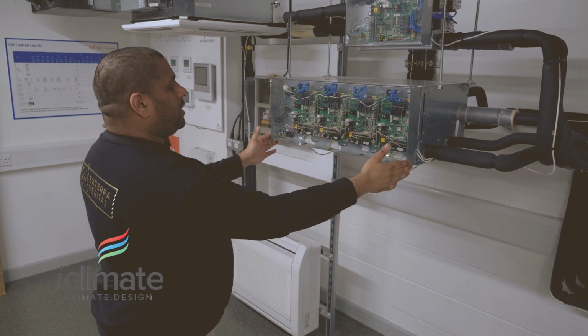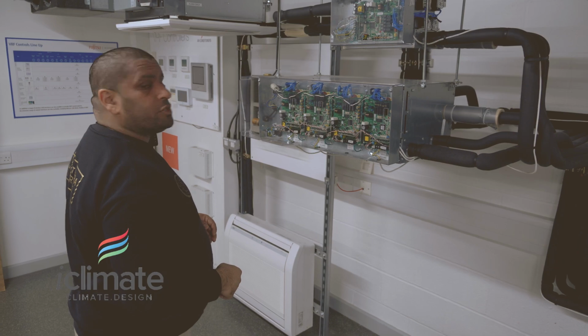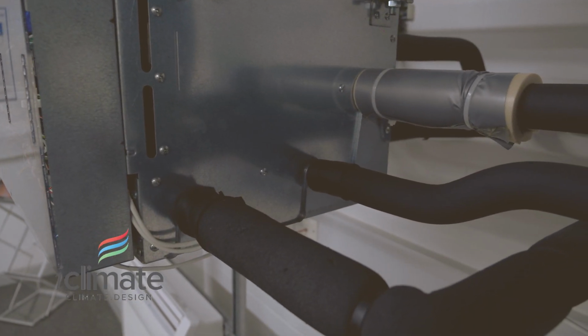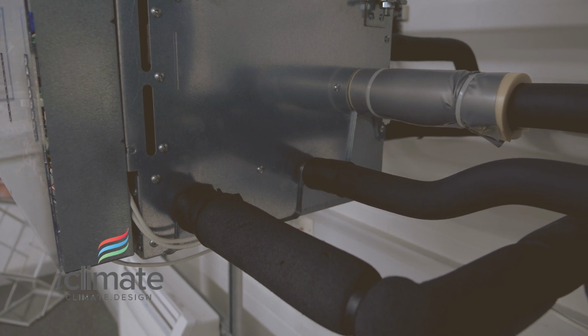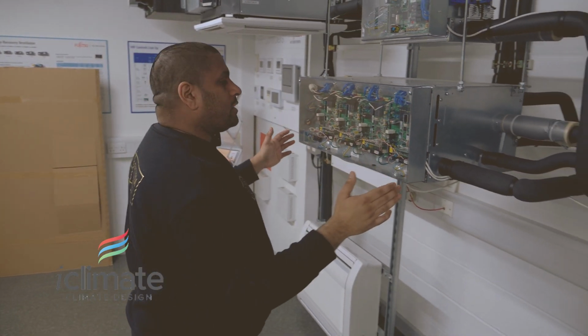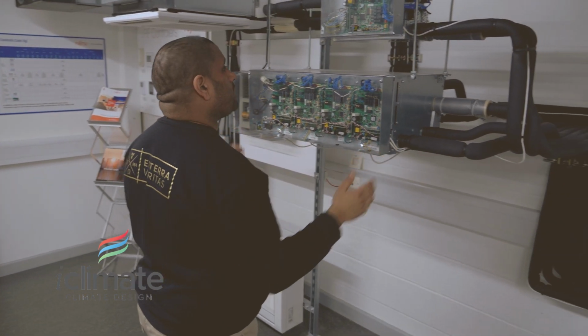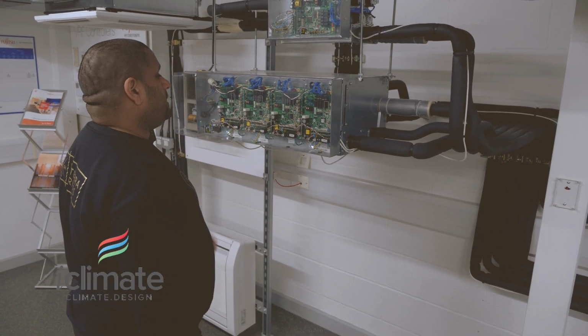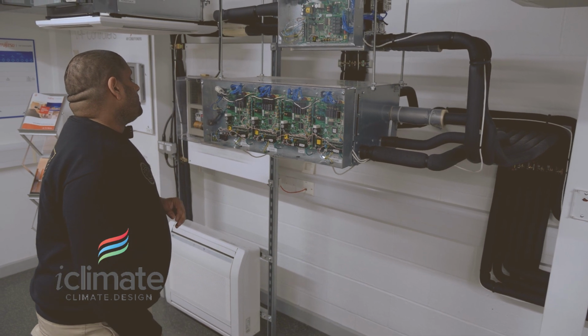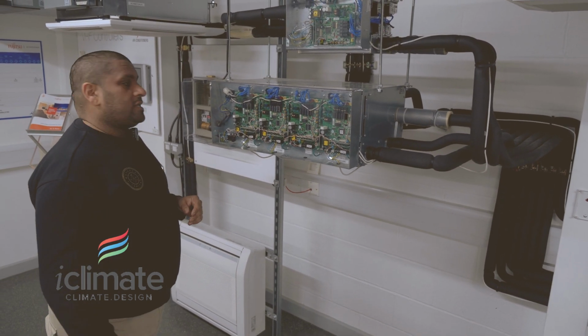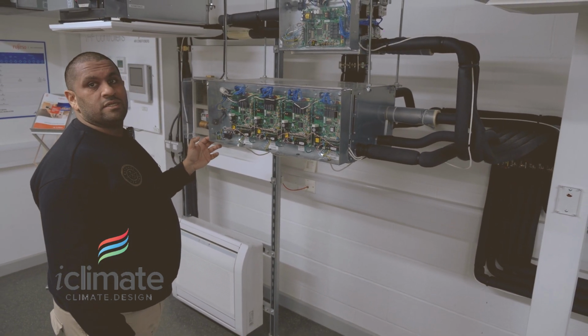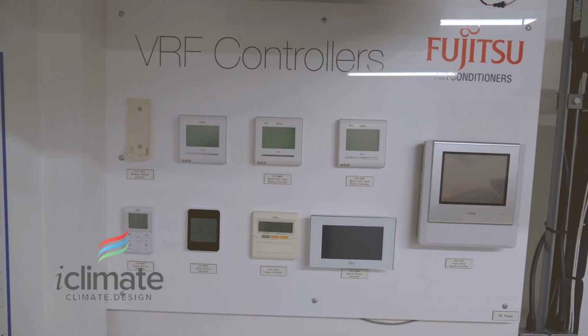So these boxes are called a distribution box. Each manufacturer has their own labeling for it, and this is the Fujitsu variant. You can see the control PCBs here and the main branch outlet here. This is for a very high, large capacity VRF system and substantially quite a large box here. This can feed up to a number of rooms inside, possibly 16 to 30. Controlling the heat recovery VRF.